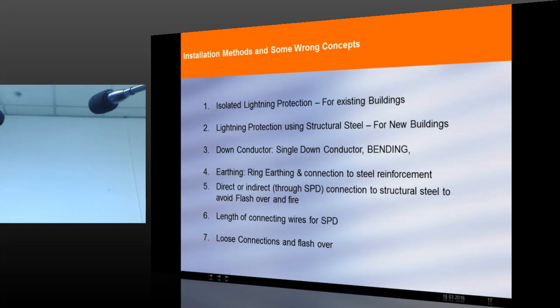For example, this particular stupa, you explained that. Maybe in earlier days, the down conductor is inside and the belief is there is no lightning strike because there is no failure. Once we made it modern and put it on the outside, isolated from the structure, then copper is stolen and then the other problems start. So now, isolated lightning protection means a lightning protection system which is not connected to the structural steel. It doesn't mean that it is isolated 1 meter or 2 meters away. No. Isolated lightning protection means a lightning protection system which is isolated or insulated from the structural steel.